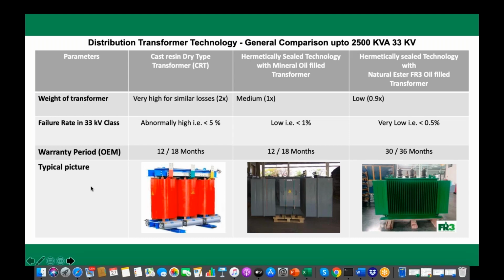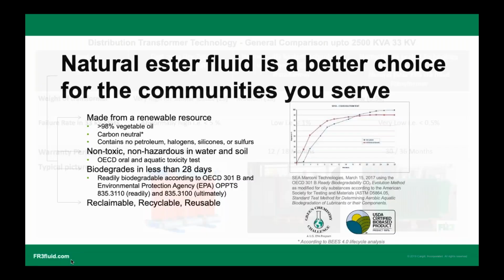So that's one of the areas, because these transformers are normally IP65, so water doesn't go easily inside the transformer into the liquid. And especially the K-class filled transformers, which are hermetically sealed, or if non-free-breathing, I would say not hermetically sealed, if they are non-free-breathing transformers, there is no chance that even the flooding water will go inside. And it is nowadays common practice for the metros that people use HT-LT connections with boots and kits, so that the connections are also screened and insulated. So let's move quickly to the next slides, and then we can open for question and answer.